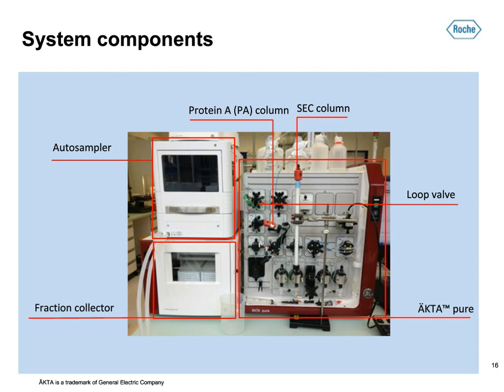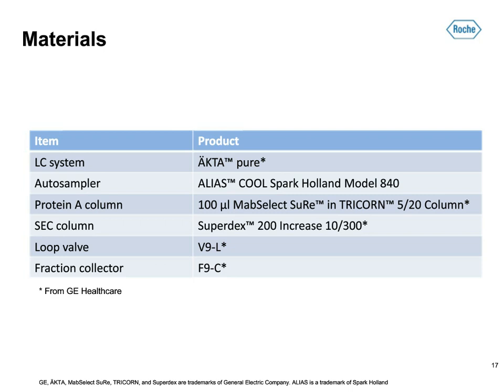Before finding the autosampler from Spark Holland, we only found autosamplers with fixed sample volumes or software connection issues with Unicorn. The big advantages of the Spark Holland model were: Unicorn has no issues with its software; we have a flexible and individually adjustable sample volume up to 9 ml; and it is coolable. The exact model is the ALIAS Cool model 840 from Spark Holland. For the protein A, we chose the MabSelect SuRe from GE, packed in a Tricorn 5/20 column with a column volume of 100 µL. We chose this small size to not get a too wide peak, as we wanted to collect just 500 µL in a loop, which is directly loaded onto the size exclusion column.